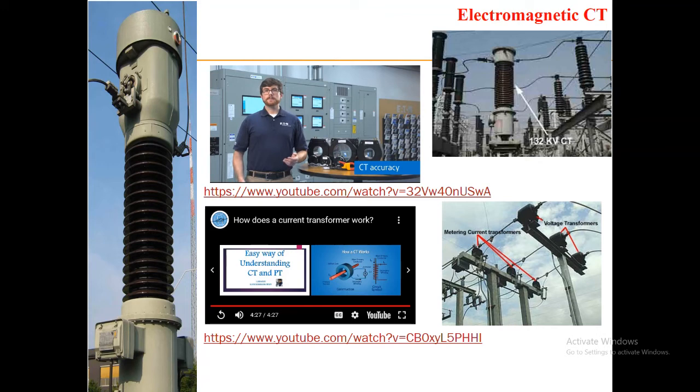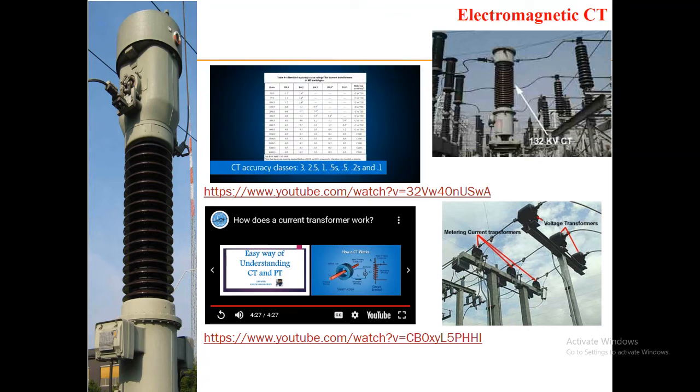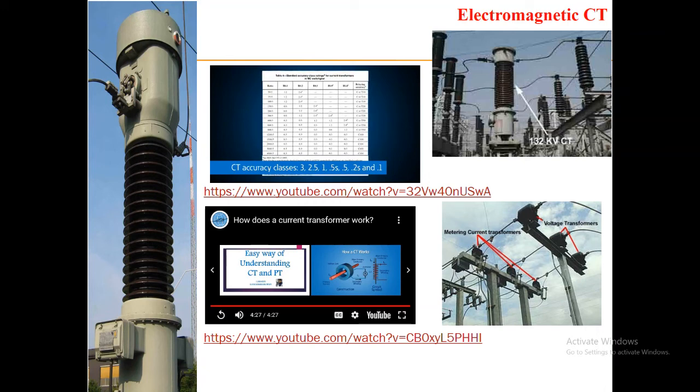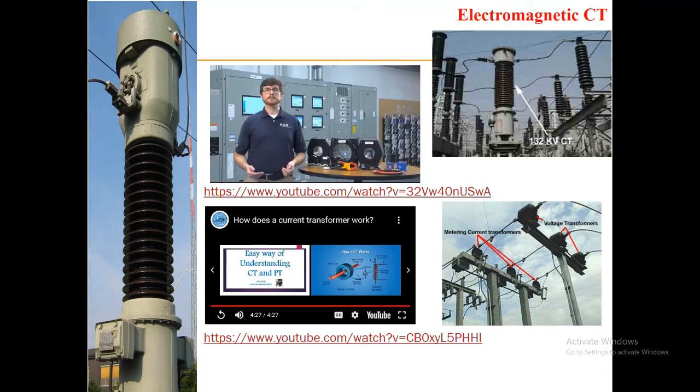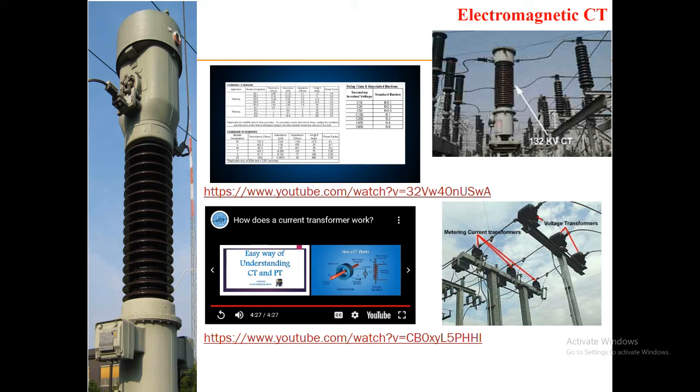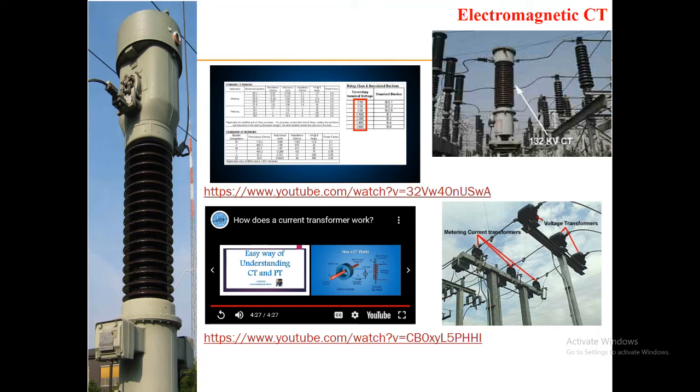Sometimes the current value is too small. A CT may not be accurate at less than 10% of its full load rating. So one way to increase the amount of current flowing through the core, especially for temporary metering, is to loop the primary wire several times through the core. For example, for a 500 to 5 amp CT or 100 to 1 ratio, looping the wire 5 times through the core will make the CT ratio 100 to 5 amps. So if 20 amps of current is flowing on the primary circuit, instead of 0.2 amps, one amp of current will flow on the secondary, making the measurement more accurate.